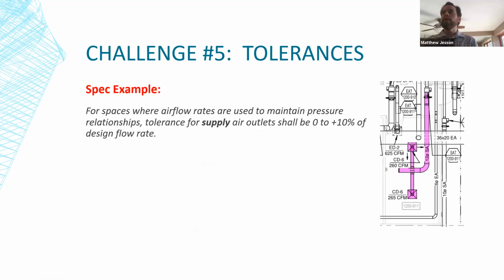Another spec example that we run into is for rooms that require pressure relationships, so labs, hospitals, etc. In this case, it says that for spaces where airflow rates are used to maintain pressure relationships, tolerance for supply air outlets shall be 0 to plus 10% of design flow rate. So if your outlet is shown with a design flow rate of 260, you may not be below that. You have to be 260 to 286, right? If I did that math right.